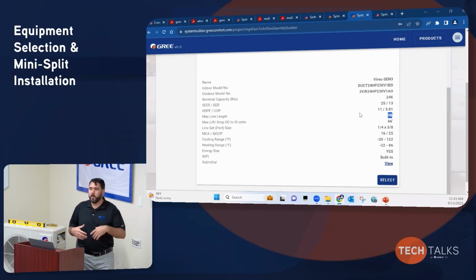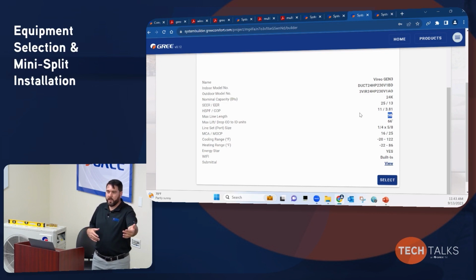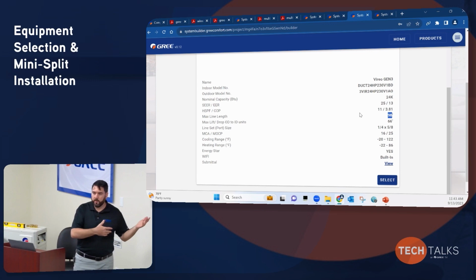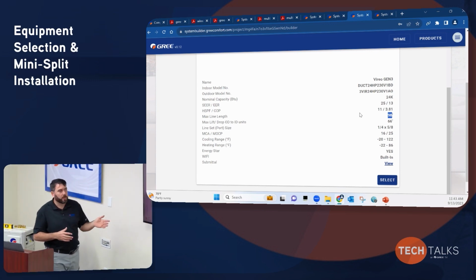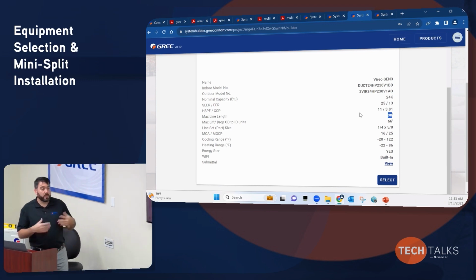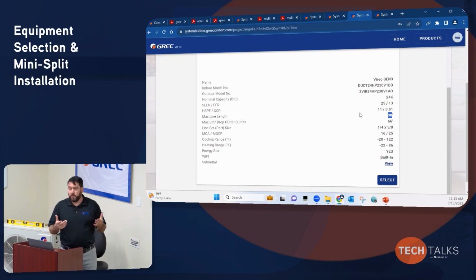What if I'm not going to be able to do that 98 feet? Say I'm at 110—then I've got to re-select equipment and choose something else that will work. Sometimes you may go from the Vireo to the Sapphire based on the available line set max length.